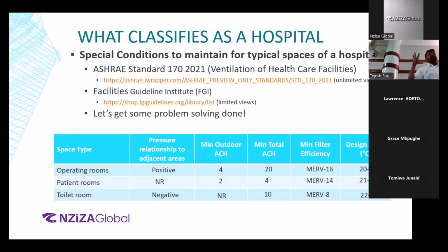What that does is, the buildings are not always properly sealed, right? So when you have a wall and a floor, there is a minute crack, in microns, that is still there, which is called the infiltration area. So the outdoor air seeps into the area and that contributes to heat loads, right? So if you positively pressurize the area, and in this case specifically the operating rooms, the operating theater, you're avoiding the outside contaminants coming into the operating space, right? Yes. That is one point.